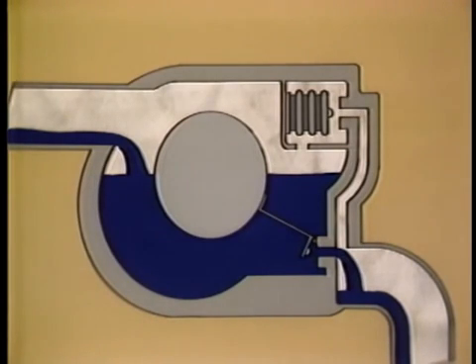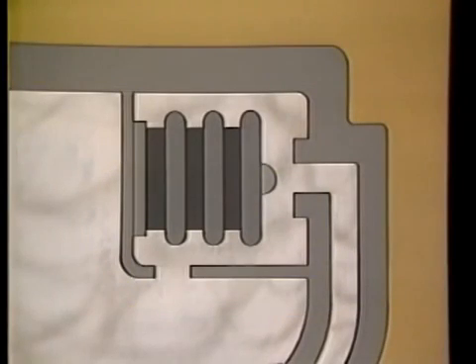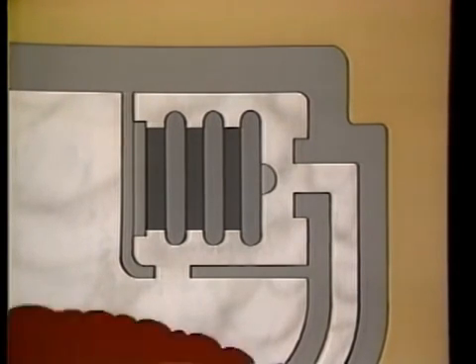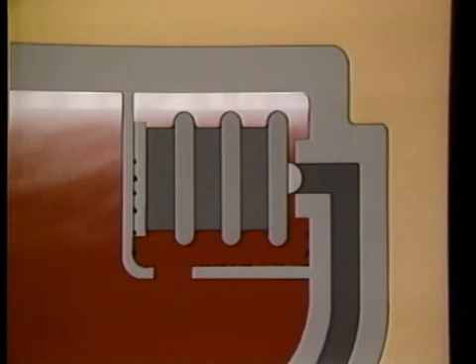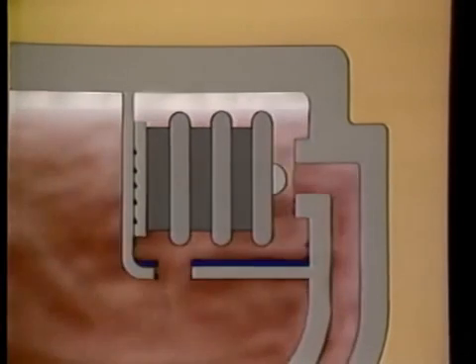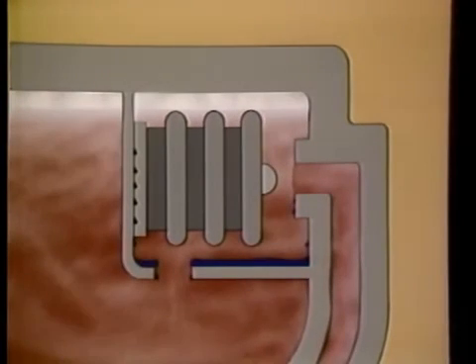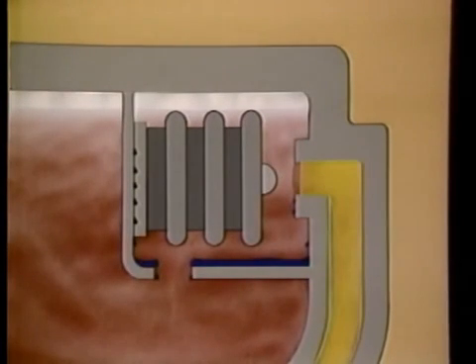Above this seal, near the top of the trap, is a thermostatic bellows. The bellows responds to temperature change. When this space is filled with hot steam, the thermostatic valve is closed. Non-condensibles, such as air, mix with the steam and cool the space near the top of the trap. When the bellows element cools sufficiently, the thermostatic valve will open and vent these gases into a passage leading to the trap discharge.